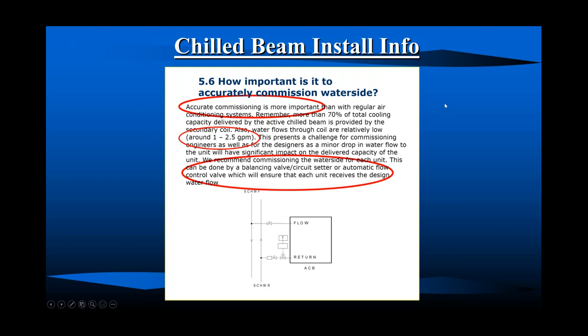And this manufacturer of chilled beam gives us a choice. We can use a balancing valve circuit setter or an automatic flow control valve. Automatic flow balancing valve, if you will. And there it is on the return of our automatic or active chilled beam. I think it's backwards. I think that isolation valve should be downstream, but it gives us a choice. So which one shall we employ to make this system work perfectly? The manual balancing valve or an automatic flow control valve?